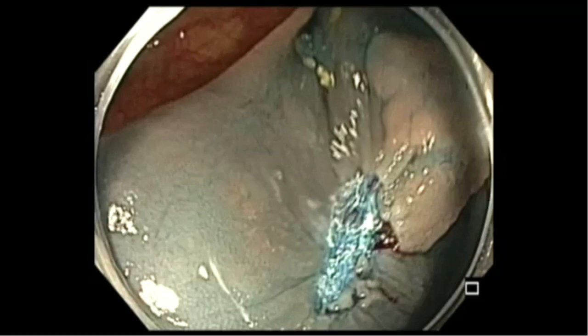So we've learned about monopolar device setup, right? And if you do a hot biopsy forceps, it's the same setup. If you use an APC, it is the same setup, except that with APC catheter, you blow some argon gas as well. And if you use a hemostatic forceps, it is the same setup. If you use a monopolar sphincterotome or a needle knife, it is the same setup in terms of how you set up the electrosurgical unit: monopolar electrode to the snare or whatever device, dispersive pad on the patient, and back to the neutral electrode on the electrosurgical generator.